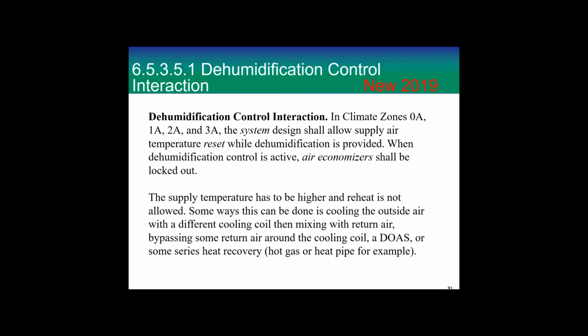And this is what they went through to say why we shouldn't care, because we can cool some of the air, just like for a VAV type system, and then we can heat it and mix it back. We can do some stuff. We can do a wraparound coil. Now, that works, but on a hot gas wraparound, you can't control the temperature you're going to come off on. Anyway, it's a problem, but it passed, it got in, and it's something you have to do. It's new, it finally got in 2019. Now, I'll just tell you a story. I was doing hospital work for a while, and I bought the best unit you can buy to control humidity, and second best.